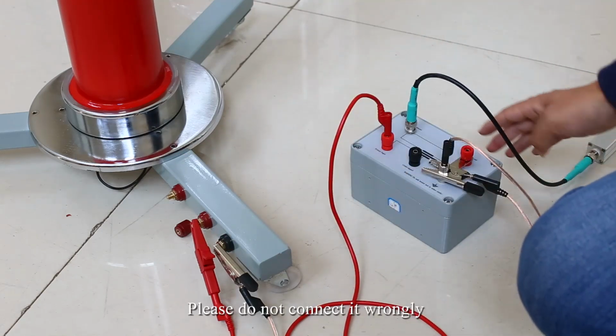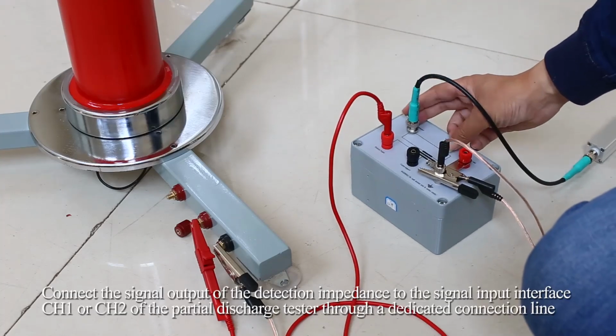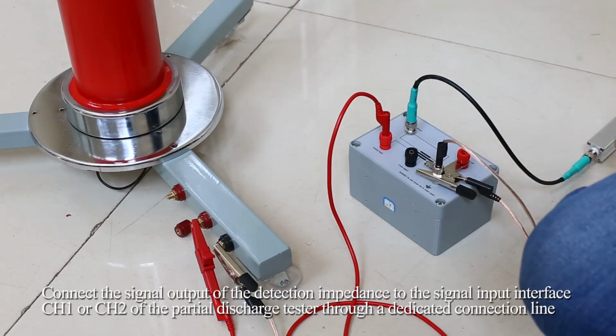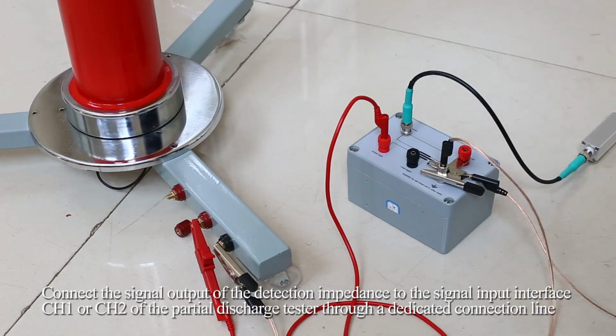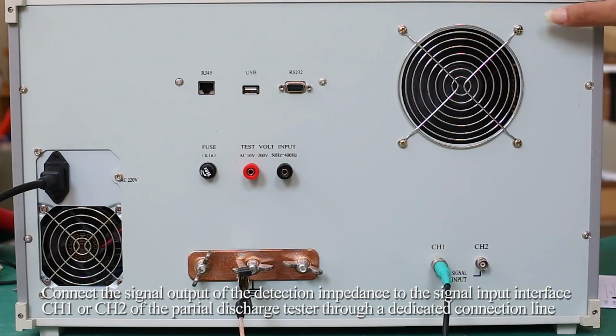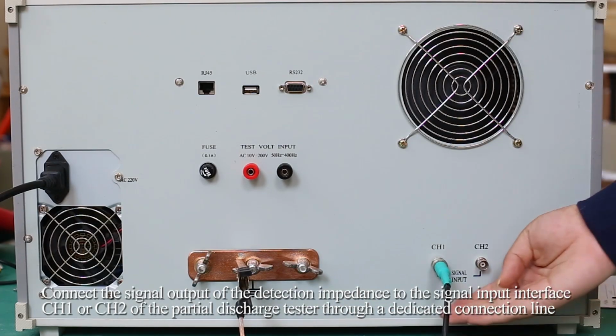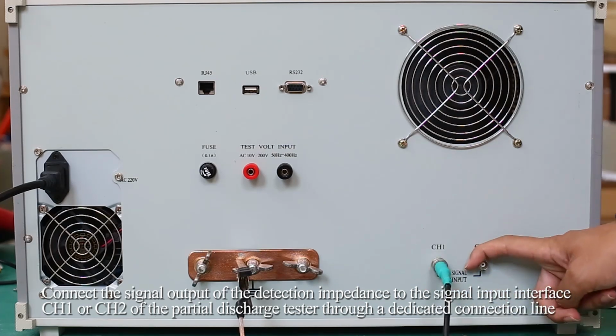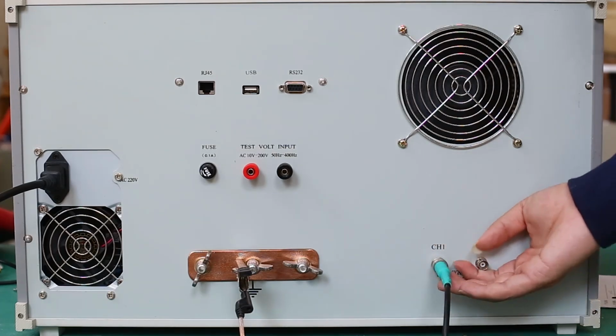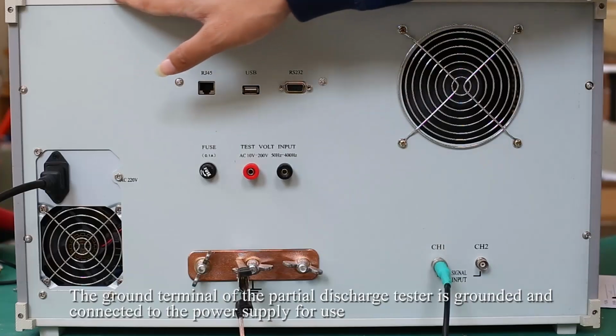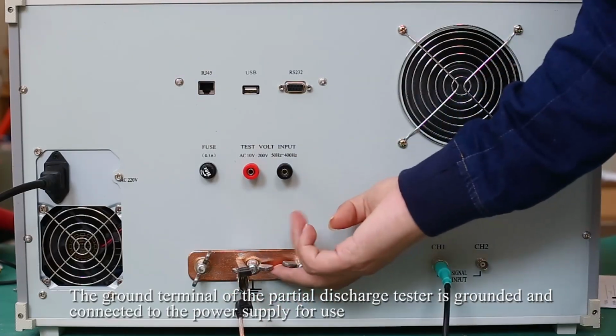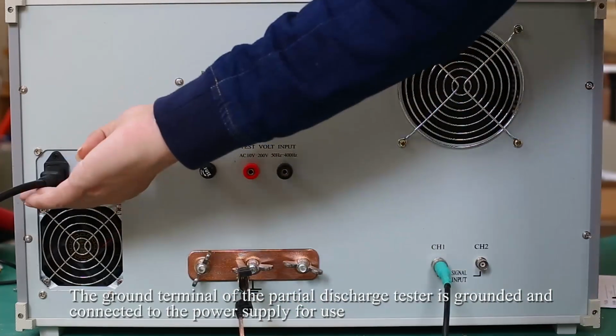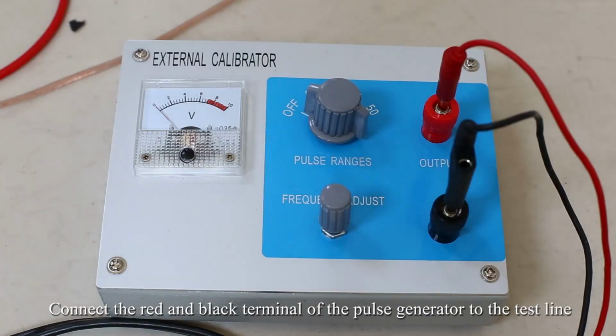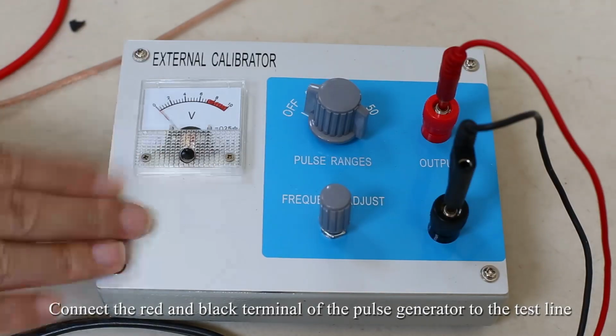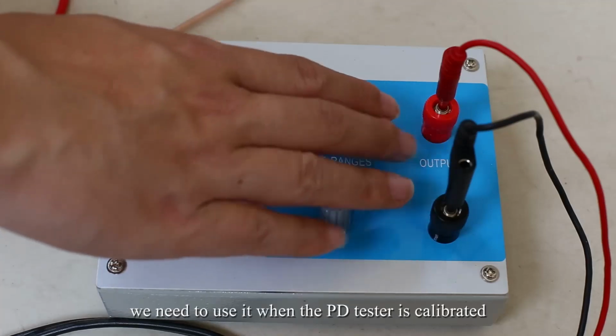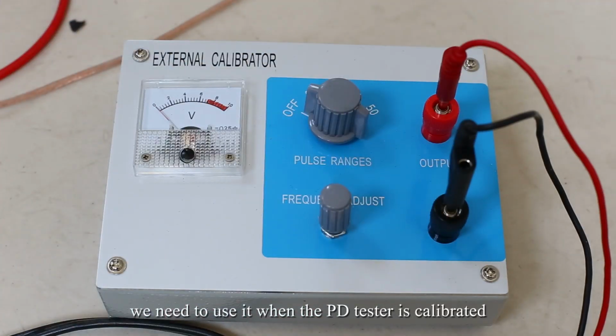Please do not connect it wrongly. Connect the signal output of the detection impedance to the signal input interface CH1 or CH2 of the partial discharge tester through a dedicated connection line. The ground terminal of the partial discharge tester is grounded and connected to the power supply for use. Connect the red and black terminal of the pulse generator to the test line. We need to use it when the PD tester is calibrated.